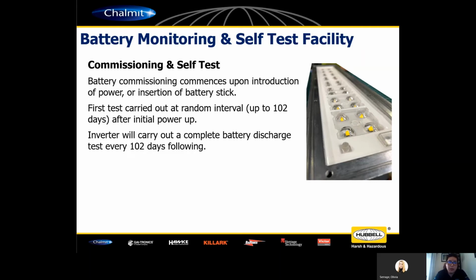The battery commissioning cycle is essentially a charge and discharge cycle, just to understand the battery memory and the maximum capacity of that battery. After it has done that, it will carry out a first test at a random interval up to 102 days after initial power up. It's a random interval to ensure that all your emergency products are not going through the self-test at the same time, so it's staggered across your facility.